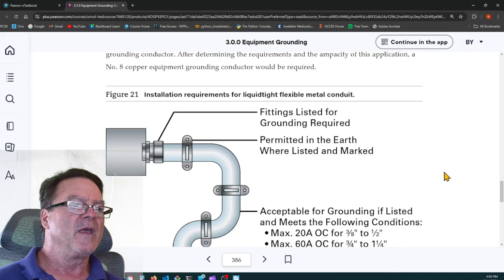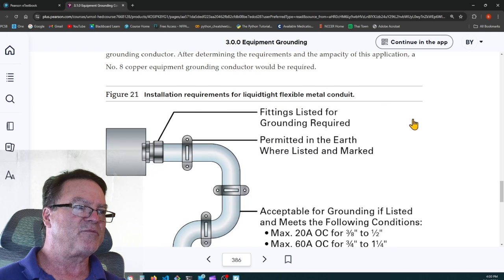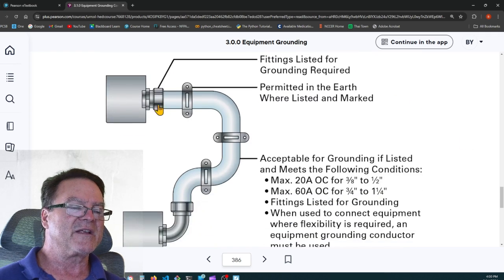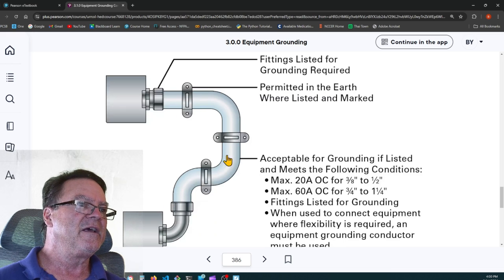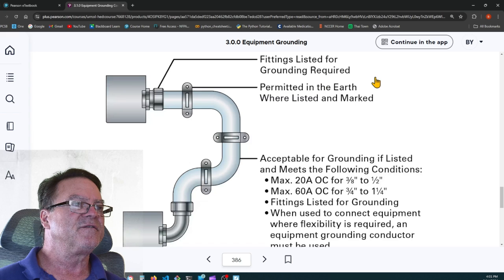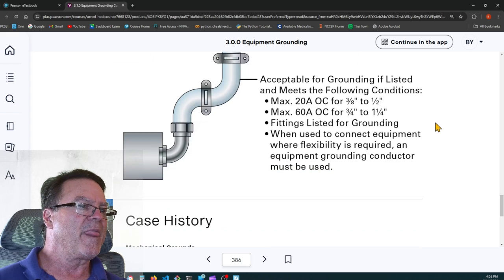All right. So here's the same conduit, but instead of being flexible, this is installation requirements for liquid tight flexible metal conduit. It's still flexible, but it has liquid tight on the outside of it. And again, you have to have a ground internal.